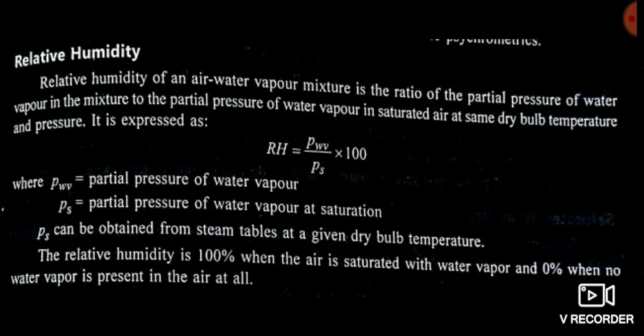Now, an important term is relative humidity. Relative humidity is the ratio of the partial pressure of water vapor in the mixture to the partial pressure of water vapor in saturated air at the same dry bulb temperature and pressure.